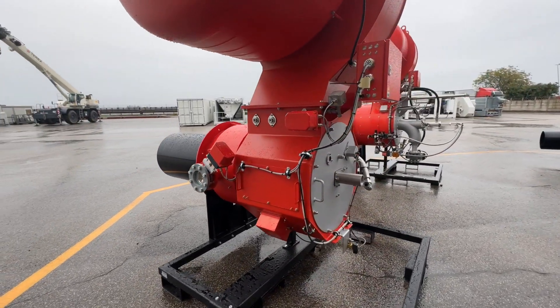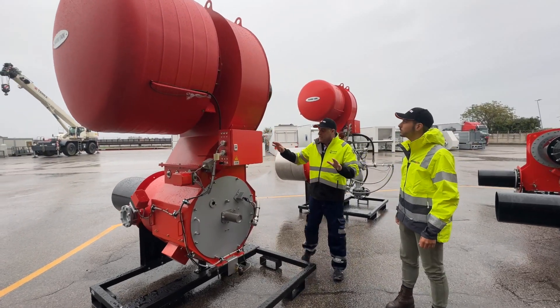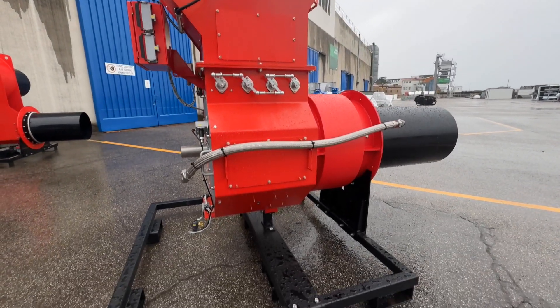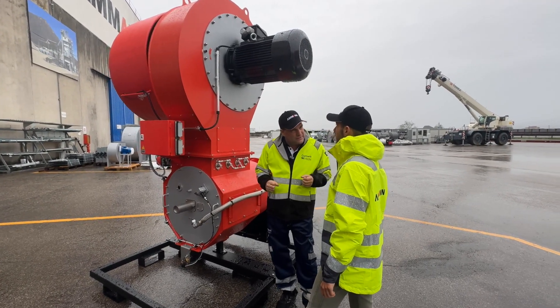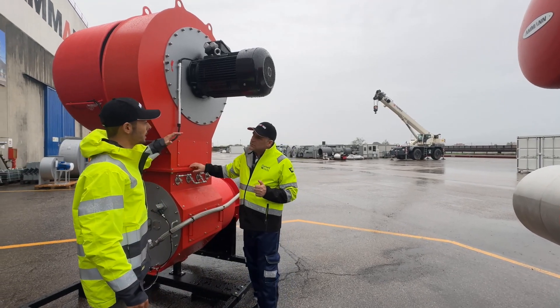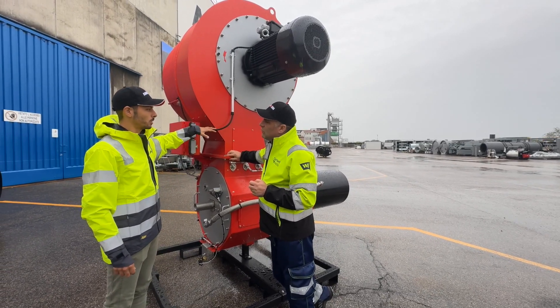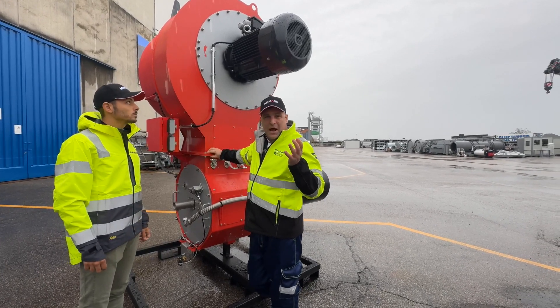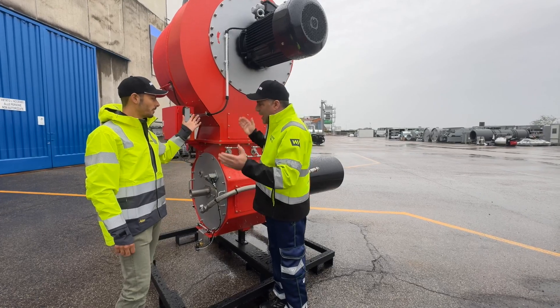We're talking about sustainability with hydrogen, and also about how this burner is controlled — control systems are in here. Another important part of being more sustainable is the electric power source that runs the fan. This is the electric drive which runs the fan. There is a frequency converter to reduce and adjust the rotation of the drive, and a sensor mounted inside to capture the RPM of the drive and adjust its velocity. That's really important for having full power from the burner, but also regulated power as the plant is operating — so we are saving energy throughout that process.